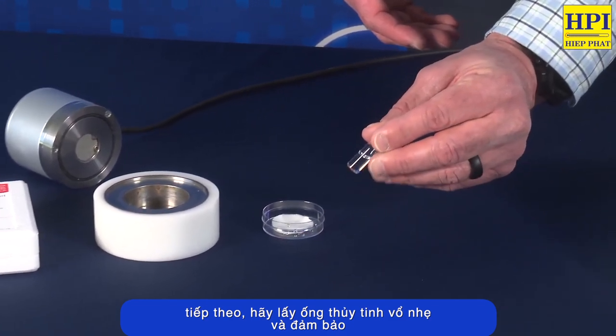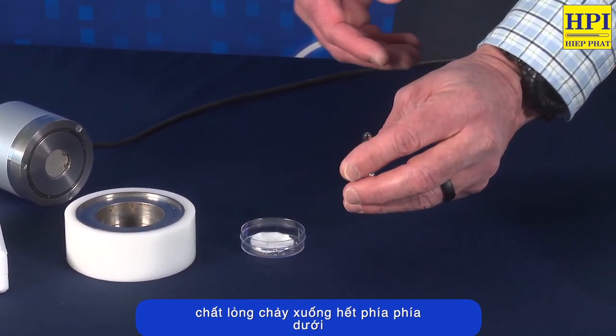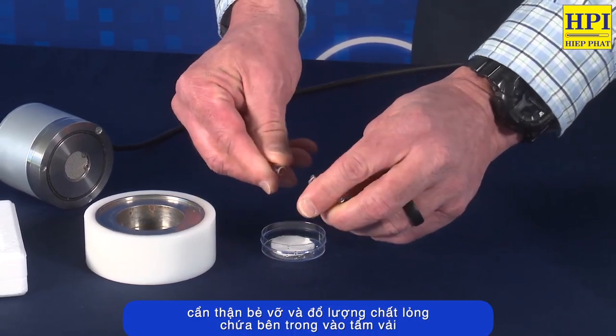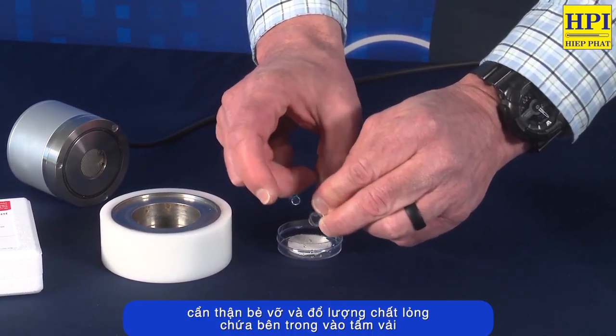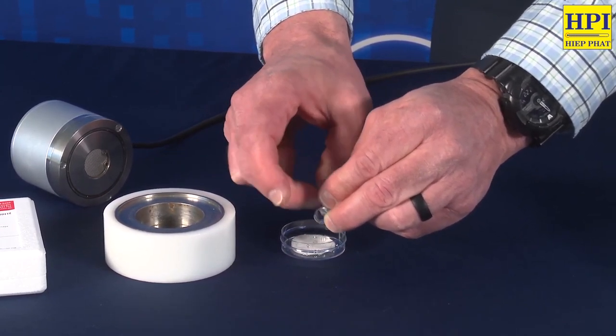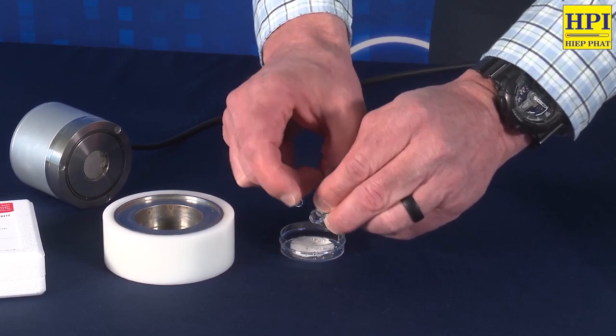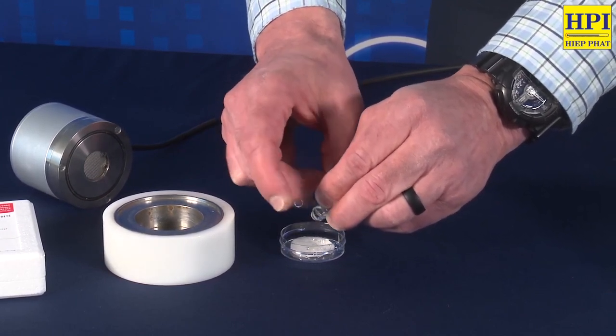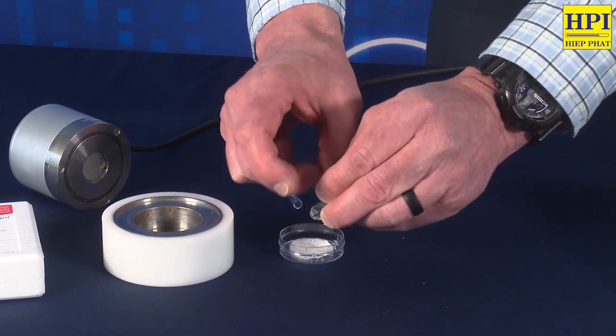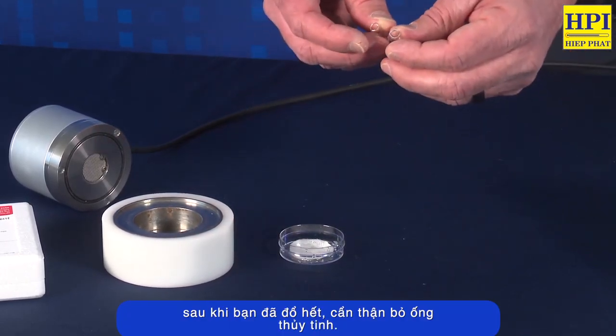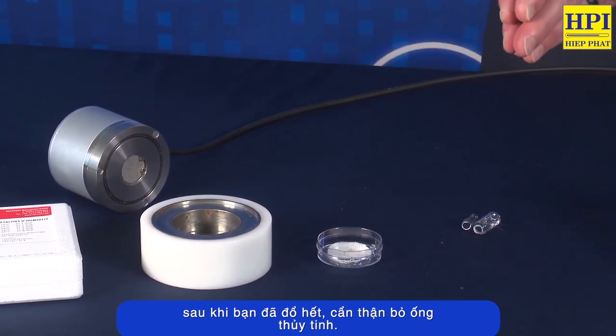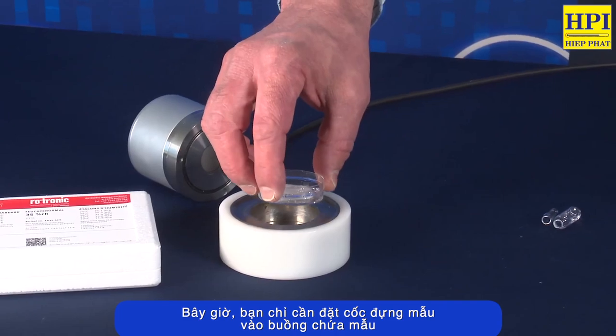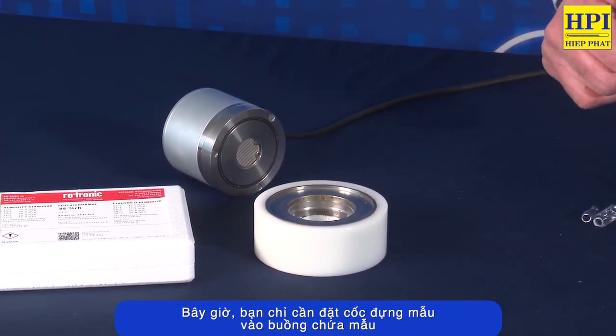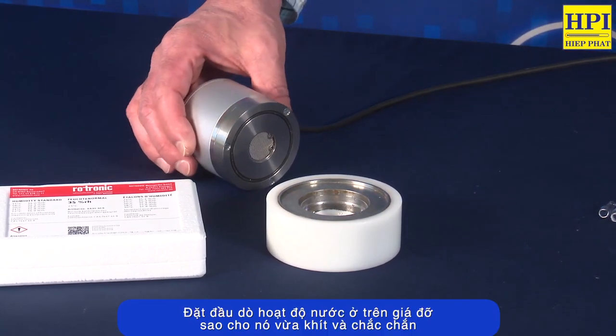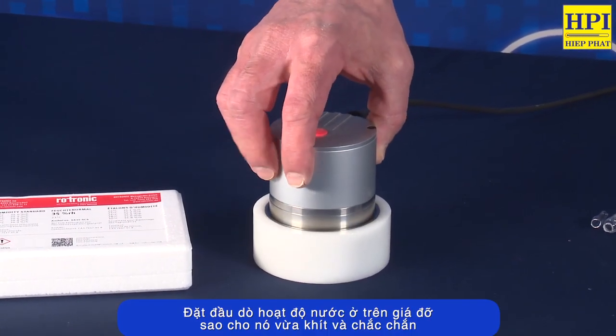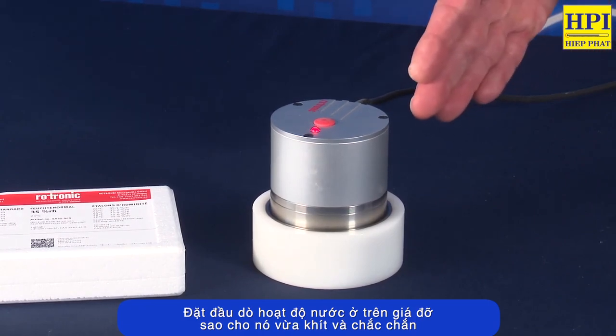Next, take the glass ampule, tap to ensure the liquid is at the bottom, carefully break at the perforation, and empty the contents onto the fiber disc pad. Once you've emptied the contents completely, carefully discard the glass ampule. Now, simply place the sample cup into the sample cup holder with the cover removed. Place your Rotronic water activity probe on top of the sample cup holder so that it fits firmly and snugly.